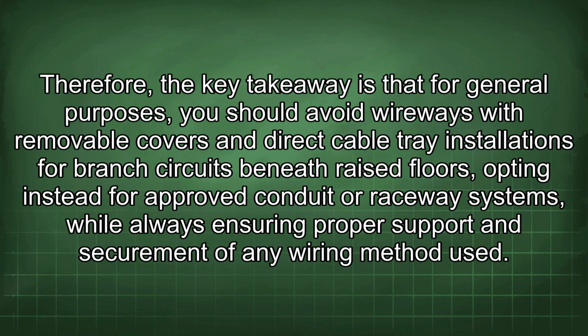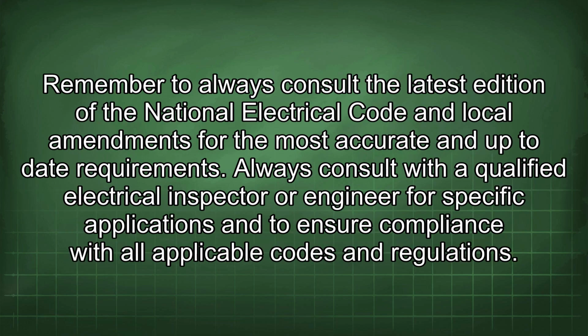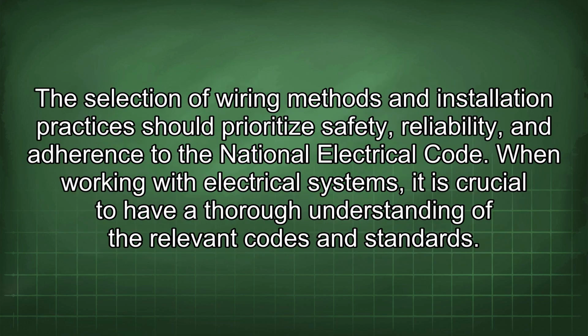Therefore, the key takeaway is that, for general purposes, you should avoid wireways with removable covers and direct cable tray installations for branch circuits beneath raised floors, opting instead for approved conduit or raceway systems, while always ensuring proper support and securement of any wiring method used. Remember to always consult the latest edition of the National Electrical Code and local amendments for the most accurate and up-to-date requirements. Always consult with a qualified electrical inspector or engineer for specific applications and to ensure compliance with all applicable codes and regulations.